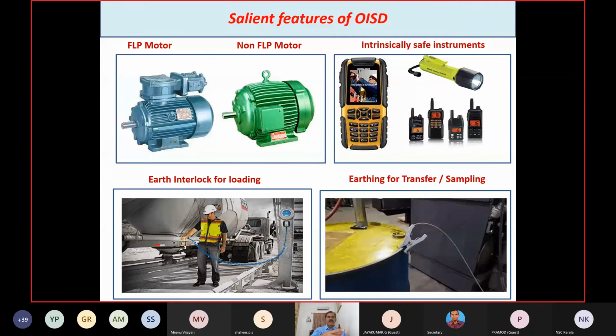Here are some examples: the FLP motor, and the next one is a non-FLP motor. FLP means flame proof. Flame proof means the enclosure withstands the explosions inside and prevents the propagation of flame outside. It has been constructed in such a manner. That is a flame proof enclosure. Intrinsically safe means the spark produced is not capable of igniting any flammable atmosphere. The current itself will be between 4 to 20 milliamps, which will not give enough intensity for creating any spark or thermal heat.